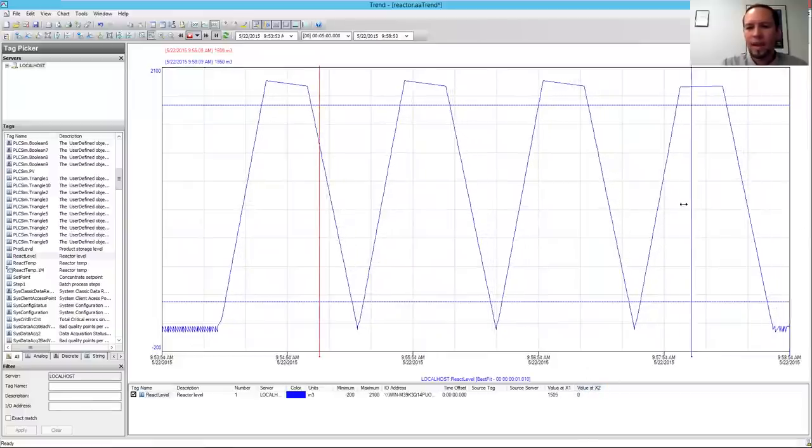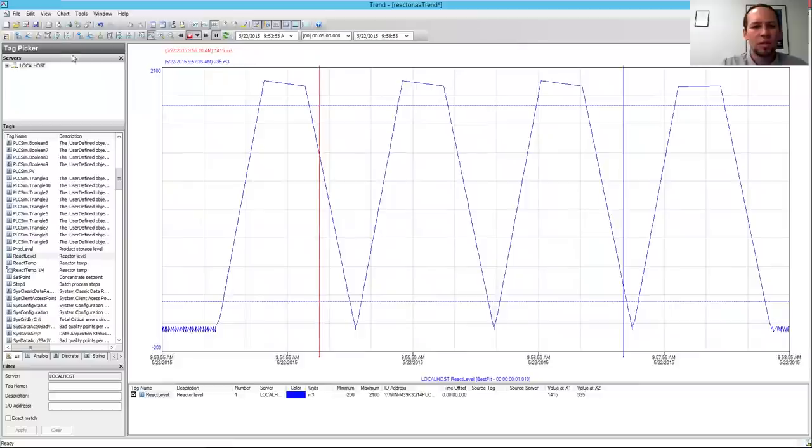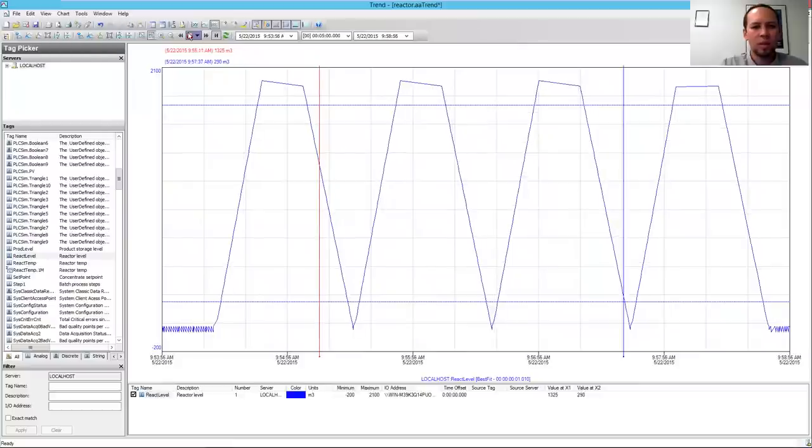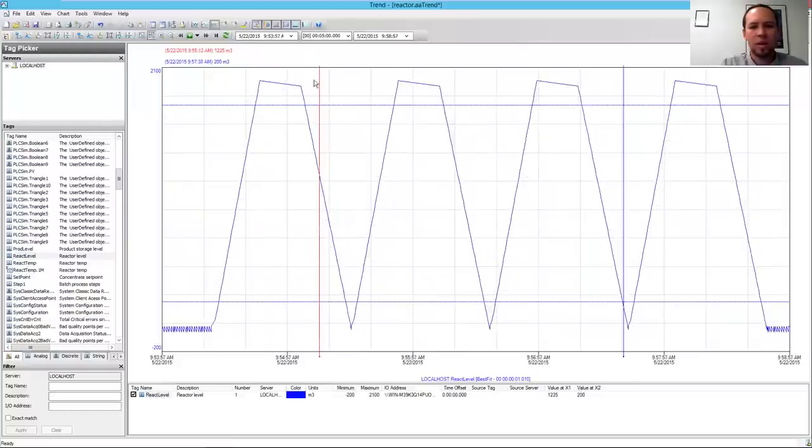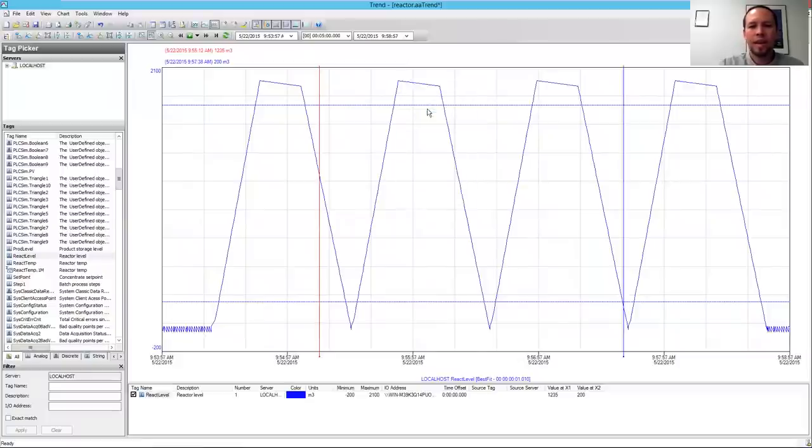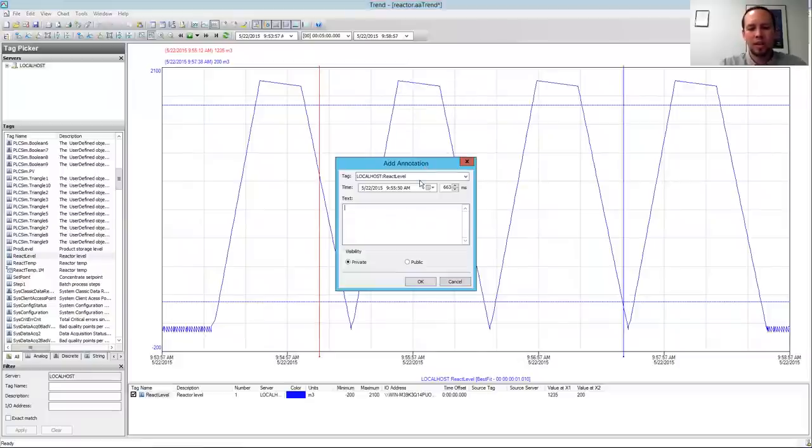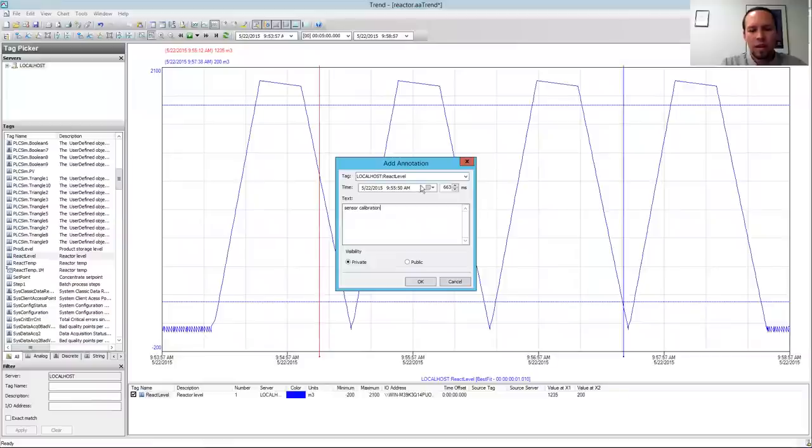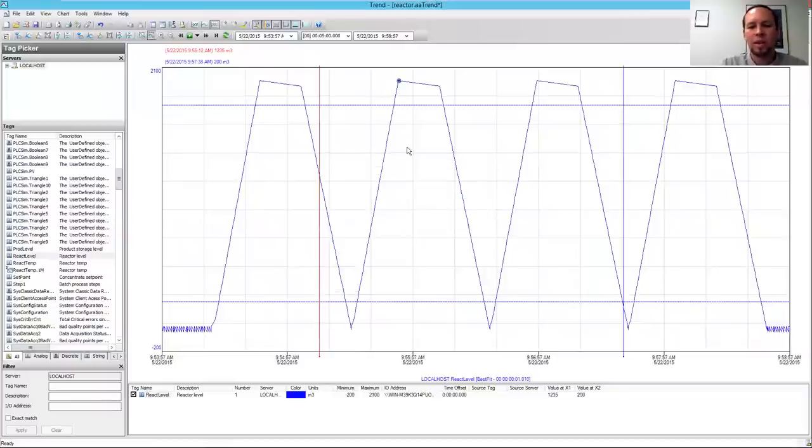I can add notes to these trends, so I'm going to stop the trend and mouse over my trend here. I can see the tag name, the value, the timestamp, the quality. I can right-click and click Add Annotation. I can say that I was doing a sensor calibration at this point in time, and if I make it a private note, only people in my group can see it. If I make it a public group, that means everybody can see it.